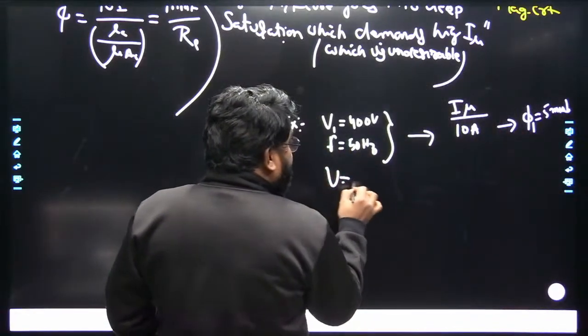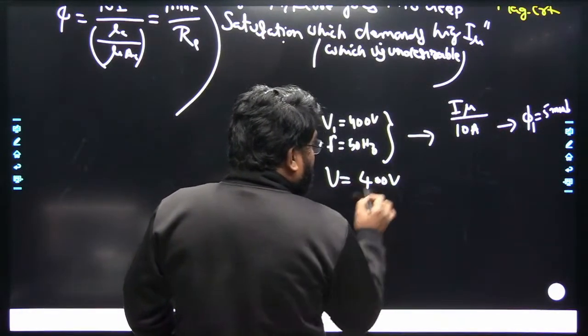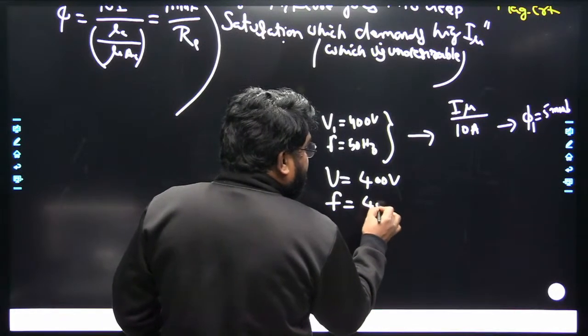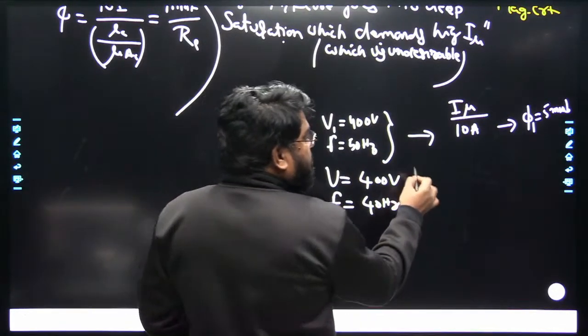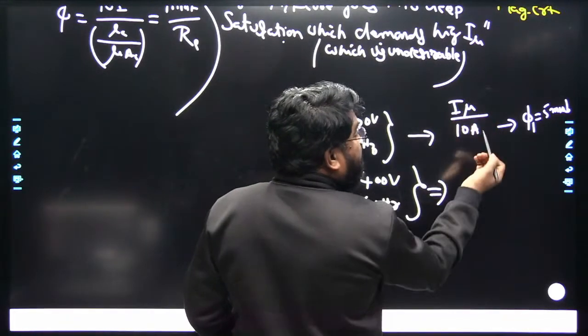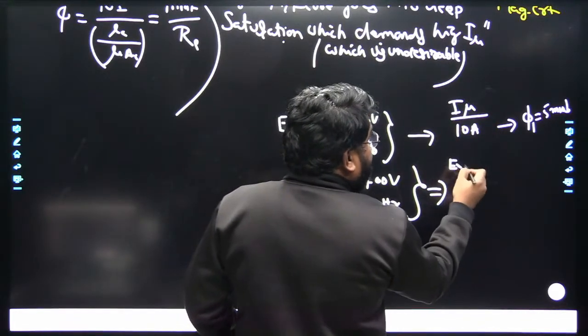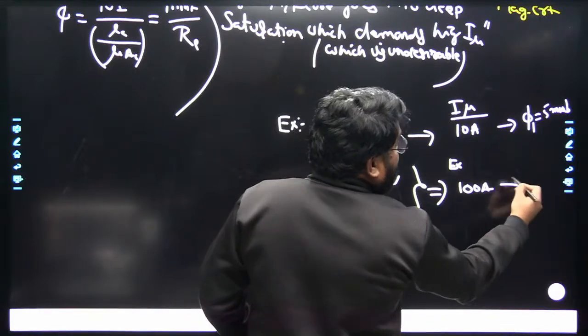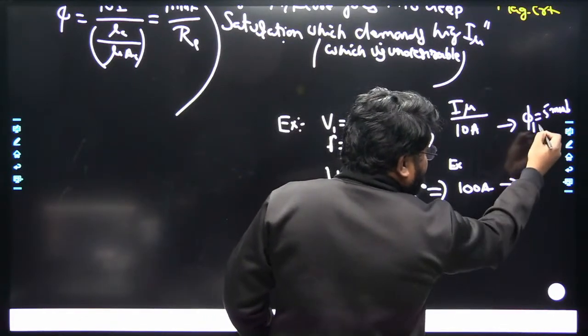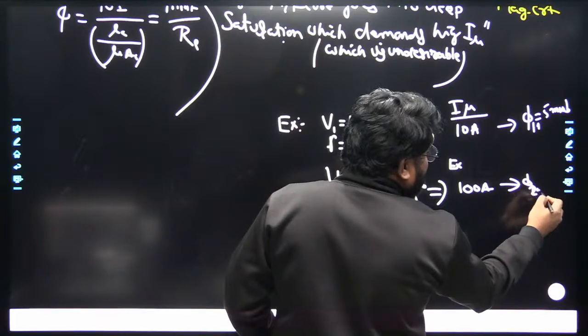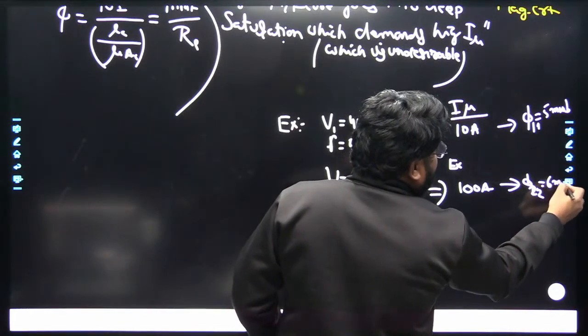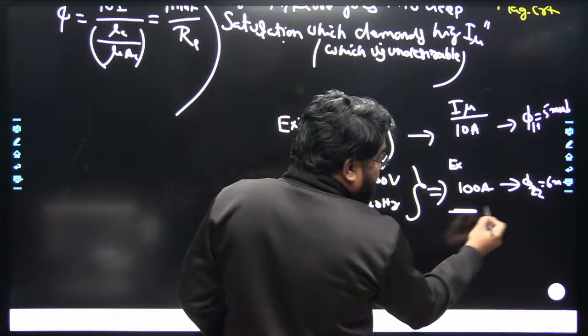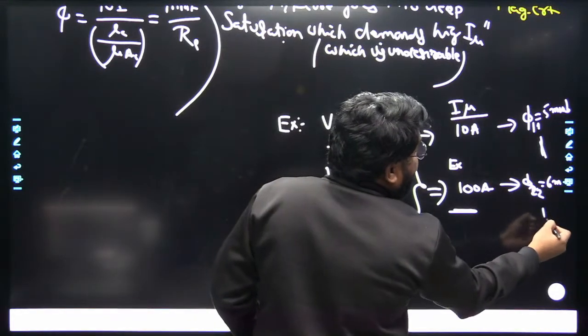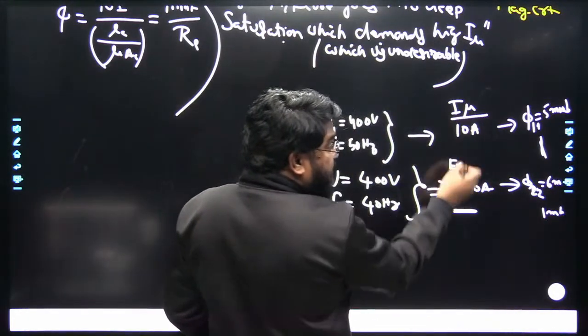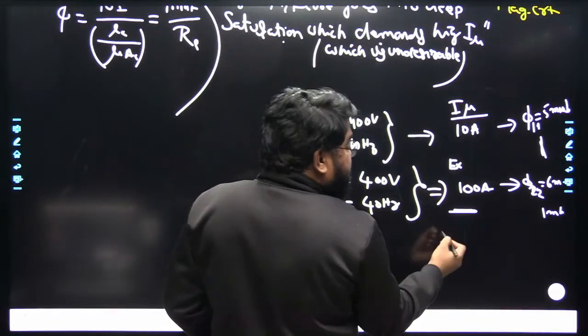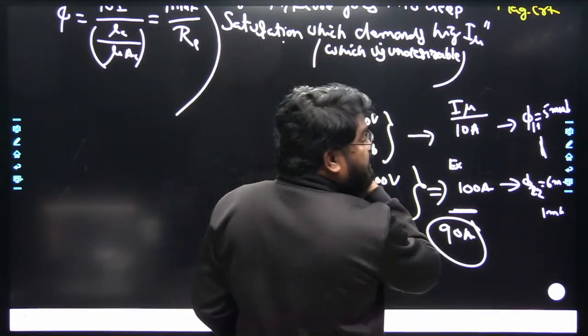Now if it is operated at V equal to 400 volts and frequency 40 hertz instead of 50 hertz, at this example point the current required is 100 amps, to create a flux of 6 milliwebers. So here the increment in flux is only 1 milliweber, but the increment in current is 10 times, meaning 90 amps of extra current is required.